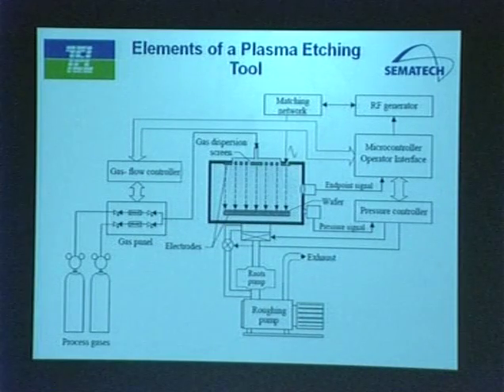Now, this shows the many components of the system. You have your plasma etcher, but that's only part of the system - there are many, many components to make that happen. You have chamber walls, and the wafer sits on a pedestal we call an electrostatic chuck. Process gas supplies go through a gas panel and mass flow controllers. To maintain a particular pressure in the chamber, you have a gate valve and pumps - turbomolecular pumps here, and in the subfab, a roughing pump. So here is the vacuum system involved in this plasma.